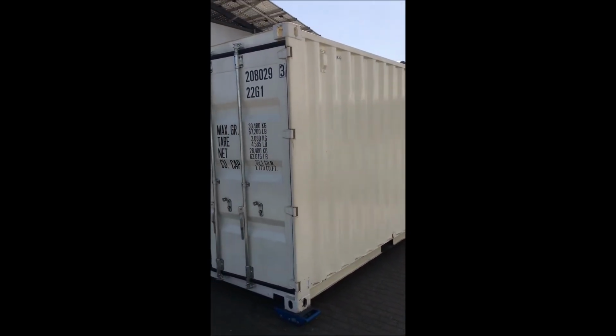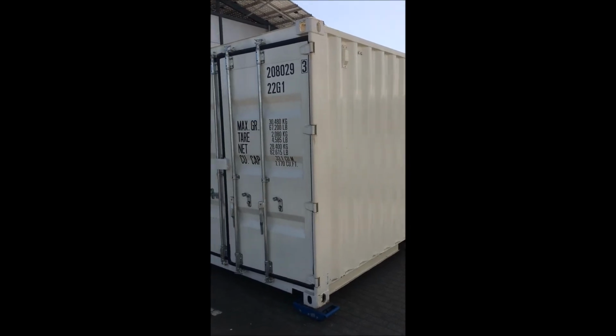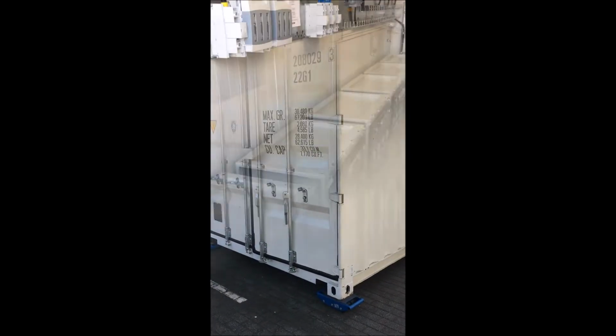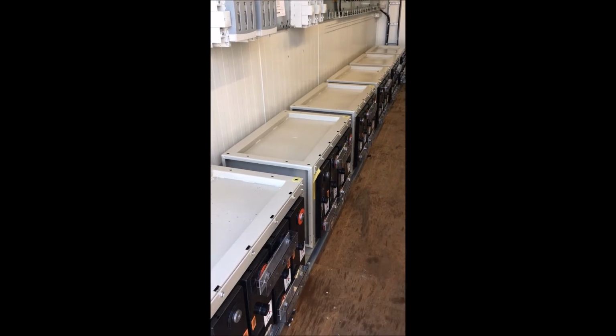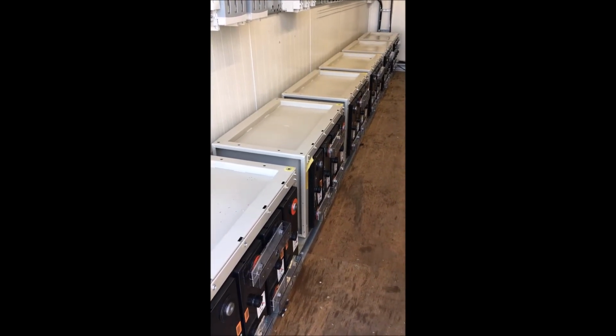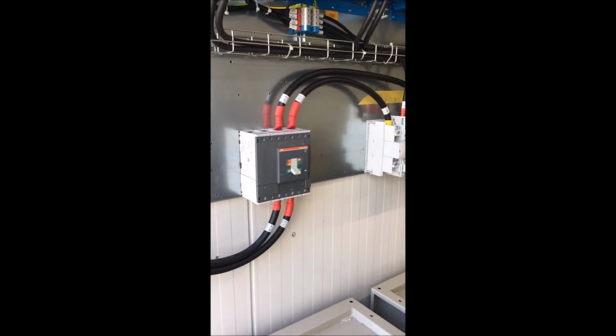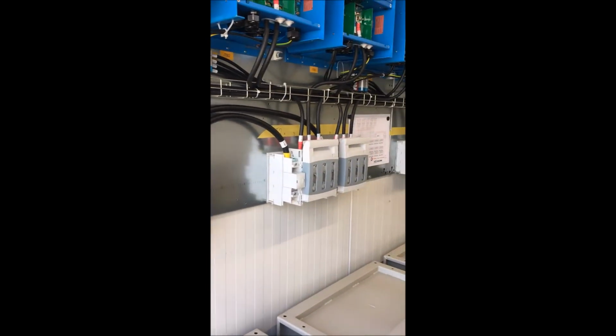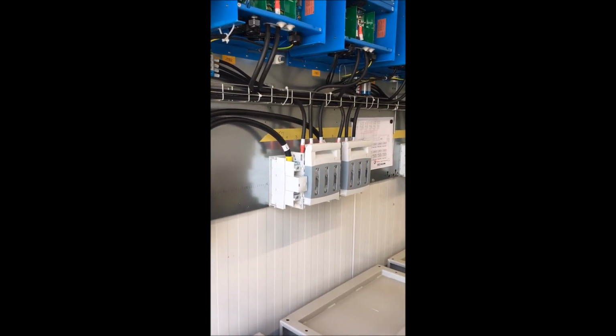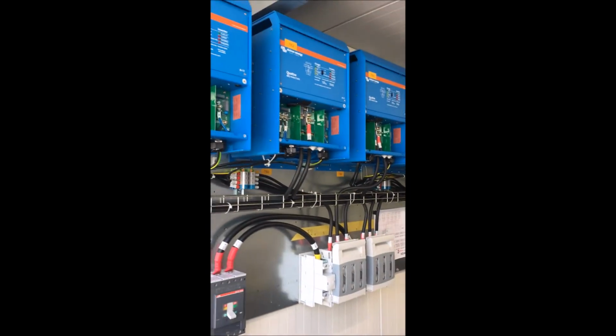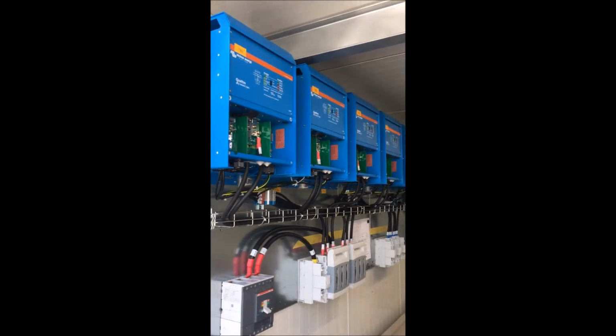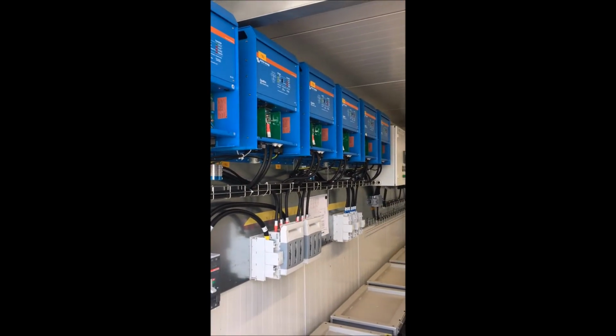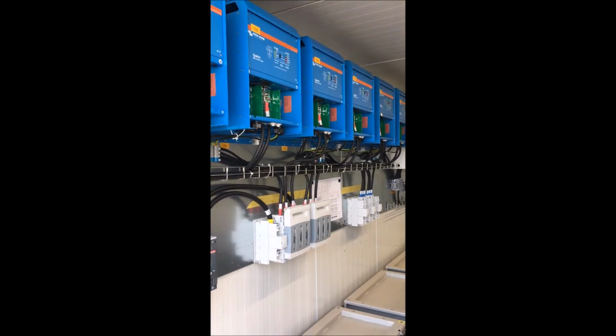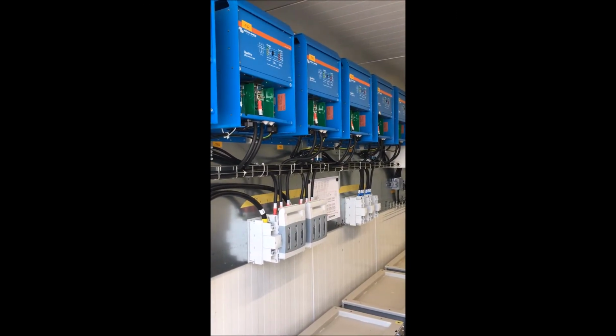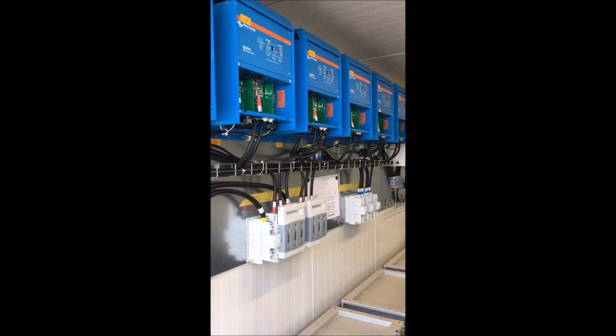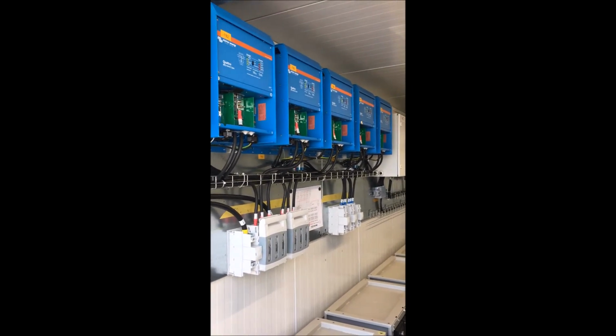The systems we're going to show you are in production for various clients in different areas of the world. Here on the bottom, you can see the battery set, which is connected to the DC bus via a circuit breaker. And from there, we go on to the DC distribution, which is then connected to the battery inverters. On the top you see we have 6 Victron Quattros, each one having a capacity of 10 kVA installed, so that the system output power is 60 kVA.